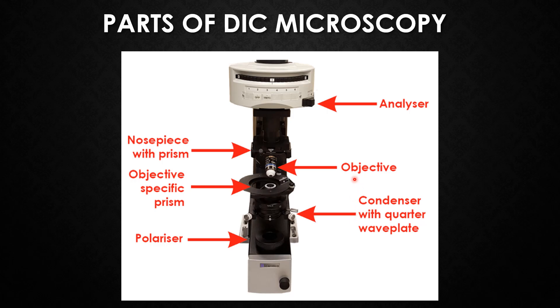The next part is the objective. Theoretically, any objective can be used, but in practice, higher grade objectives like fluorite and apochromate types are generally specified to benefit from the high resolution potential. In many cases, phase contrast fluorite objectives are chosen, permitting brightfield, DIC, phase contrast, and fluorescence observation with a single set of objectives.